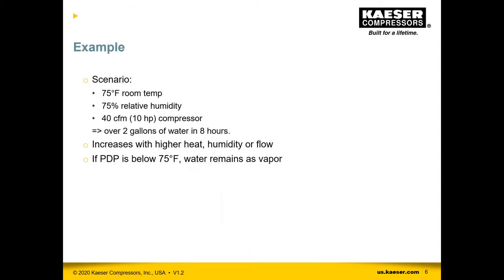To put it in perspective: on a 75-degree day with 75% relative humidity and a 10-horsepower compressor pulling about 40 CFM, in an eight-hour workday you might pull two gallons of water into the system. Of course, higher humidity and higher flow means more water. The hotter it is, the more humid it is, and the more air you're using, the more water you're putting into your compressed air stream. If you keep the compressed air temperature below the ambient temperature — in this case 75 degrees — the moisture in that compressed air will stay as a vapor. That concept becomes important when we talk about dryers.